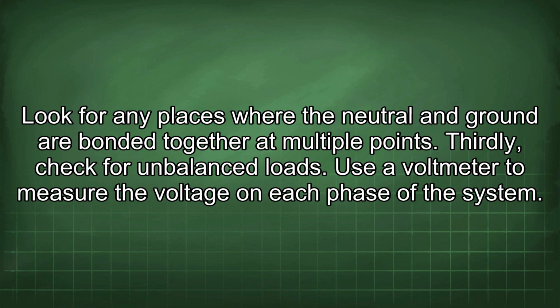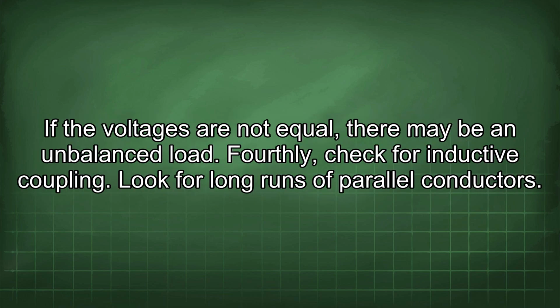Thirdly, check for unbalanced loads. Use a voltmeter to measure the voltage on each phase of the system. If the voltages are not equal, there may be an unbalanced load. Fourthly, check for inductive coupling. Look for long runs of parallel conductors.